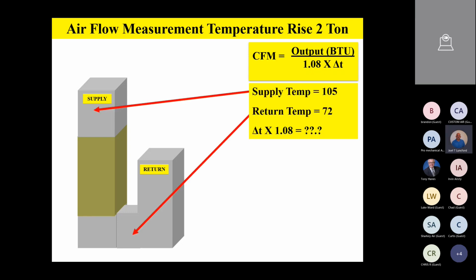Now watch this. I take my temperature probe, and I see that my supply air temperature is 105 degrees in this example. My return air temperature is 72 degrees. So I find the difference between 105 and 72. 105 minus 72 gives us a temperature difference of 33 degrees. But hang on a second, we're not done with that yet. So we take that 33 degrees times 1.08, and that gives me a number of about 35.6. That 35.6 is the number that goes on the bottom of the calculation. So let's write that down.